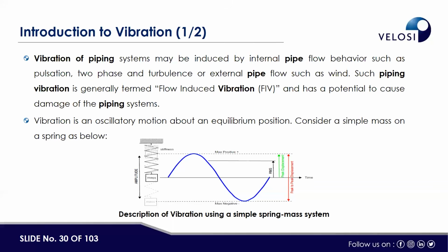What is vibration? Vibration of piping systems may be induced by internal pipe flow behavior, and these flow behaviors can be described as pulsation, two-phase, and turbulence flows, or it might be caused by external pipe flow such as wind. Such piping vibration is generally termed flow-induced vibration and has the potential of causing damage to the piping systems.